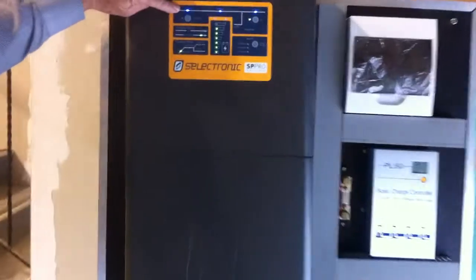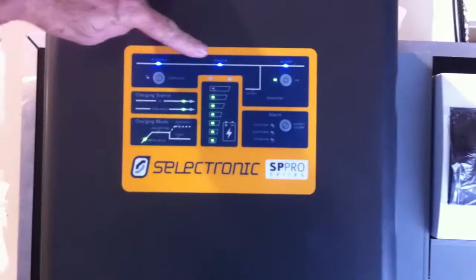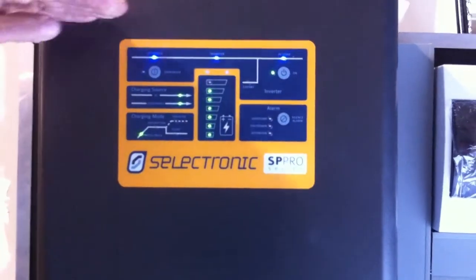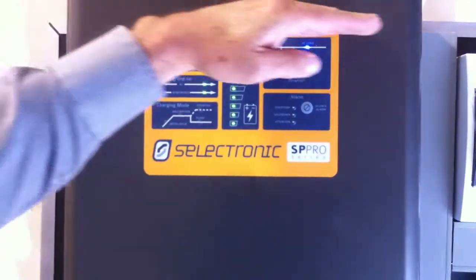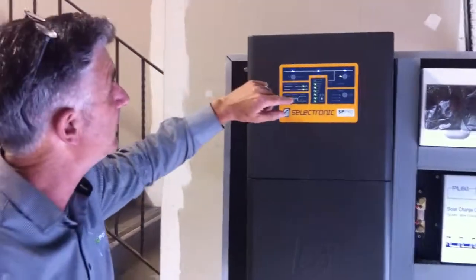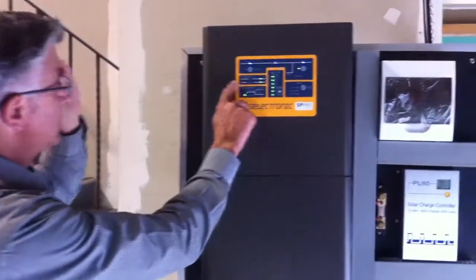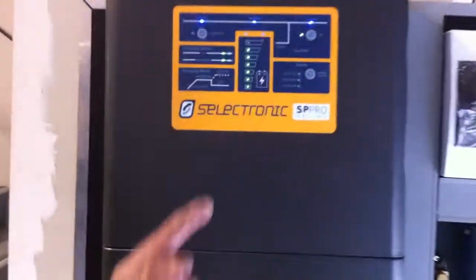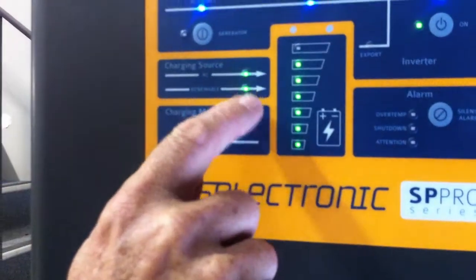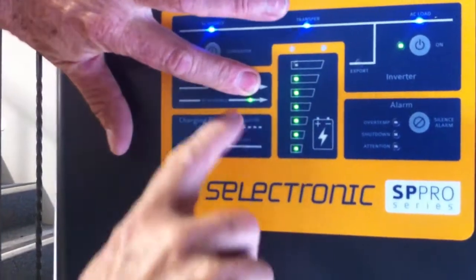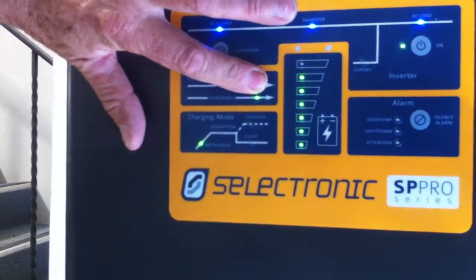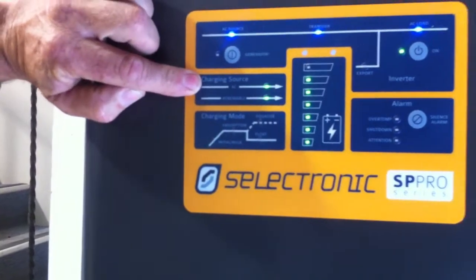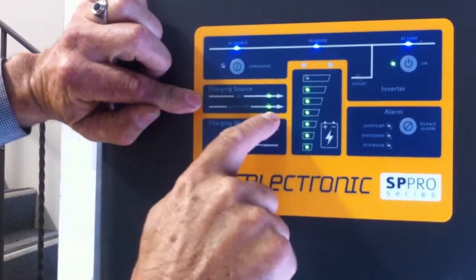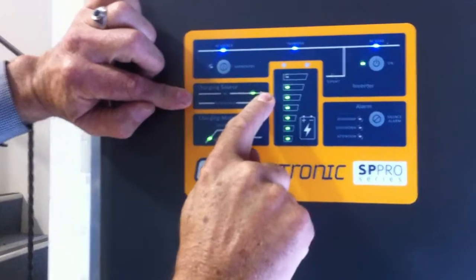And if you see the SP Pro, suddenly now it recognises that there's an AC load, then it goes to a transfer light. So what it's doing is it's feeding your load, and simultaneously it's charging the batteries. You'll notice here where it says charging source, before we plugged in that AC load, the only charging source it knew was renewables charging. But now that we've plugged in the AC load, renewables are charging and your generator's charging.